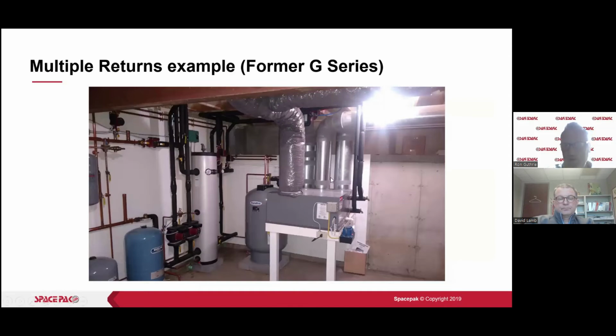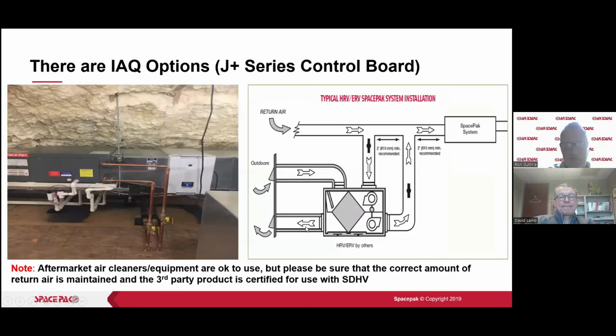Multiple returns. Here's one with 3 returns, right, and a plenum on it. Incidentally, this is an older unit where we used to be able to convert a horizontal unit to a vertical unit, but when we started putting EC motors in there, the motor head didn't give us enough room and didn't quite work with doing this. So if you see this in the field, you would just want to put a vertical unit in place of that, or exit horizontally and turn vertical. This is also an example of a side shot. We'll talk about that. And that's it in that picture.